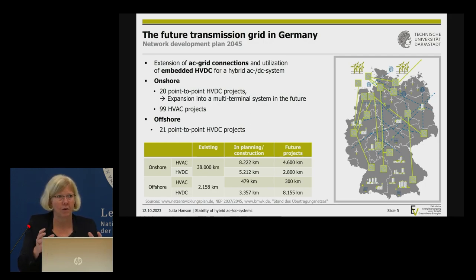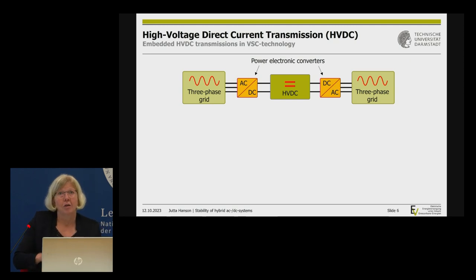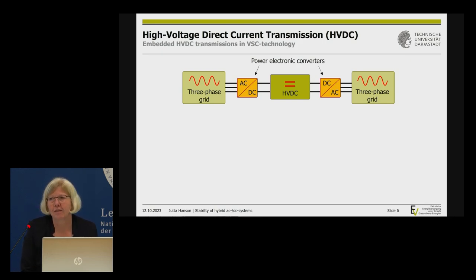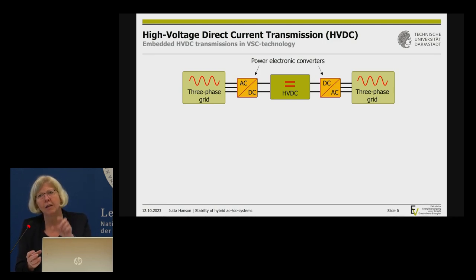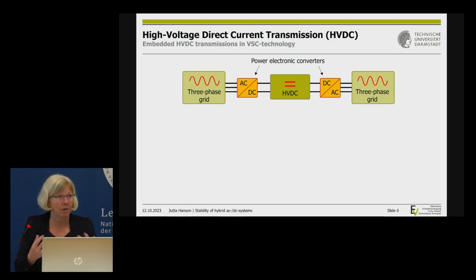HVDC works by taking our three-phase 50 Hz AC system, converting it to DC with a power electronics converter — effectively reducing frequency to zero — transmitting over a long distance, then converting back to three-phase 50 Hz at the other end. Most of the projects use VSC technology — specifically self-commutated converters — at a voltage of plus/minus 525 kV and a rating of 2 gigawatts.